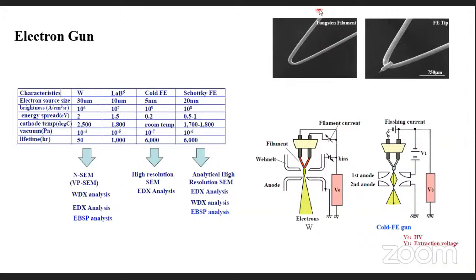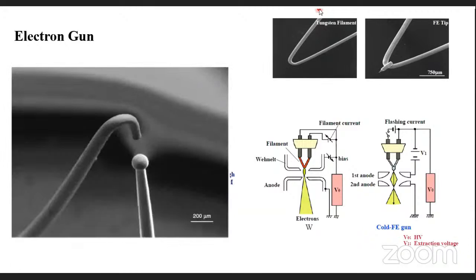Even after three or four years of use, we still get some good images, but the quality of the image will reduce. What happens to the gun is it will break and we can see separation — it loses efficiency in emitting electrons. The electron gun is very important. You can see the tungsten filament and a field emission tip with a small needle-like structure. The tungsten filament is used for thermionic emission, while the other is used for field emission.